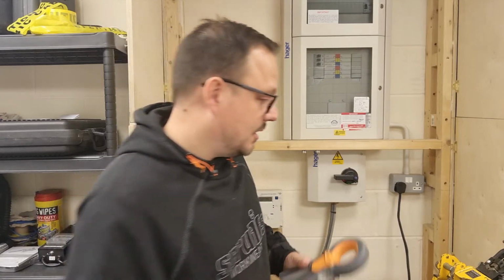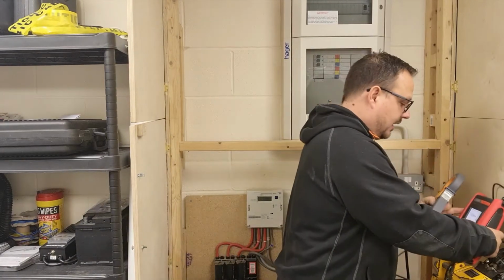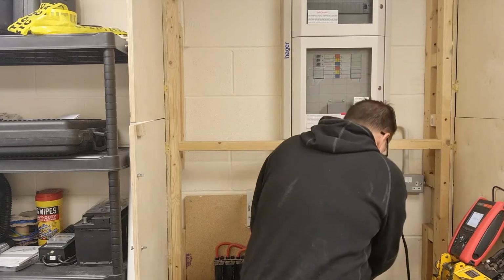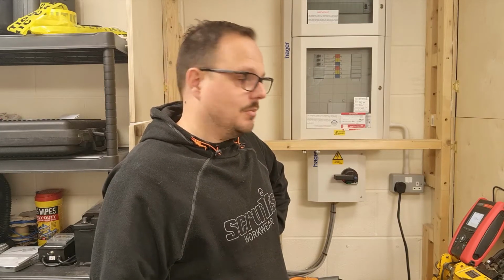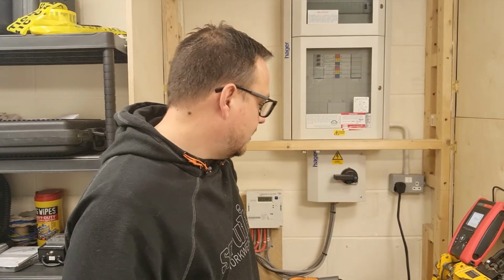This records both. I'm not going to split these cables apart to demonstrate that on this 3-phase head, but yeah, it's a handy feature, and again those results are savable, so you can go into a property, quickly take those measurements and save them and have a little look later. So when you're prepping your quote, thinking this EICR before consumer unit change is maybe going to take me a little bit longer than something where you're not, you know, we all get a feel for it, don't we? When you measure for the earth leakage, you know that something's maybe going to take you a little bit longer than it otherwise would, because there's a few gremlins in there to find. And yeah, that's that one really.